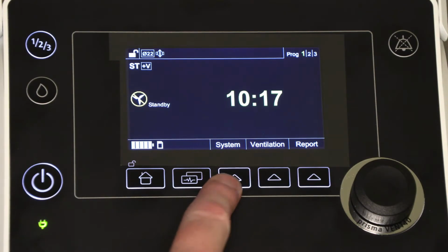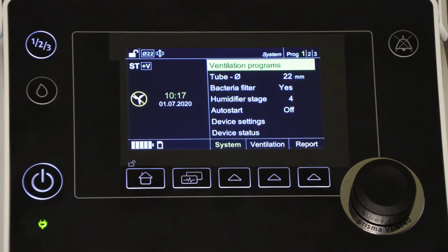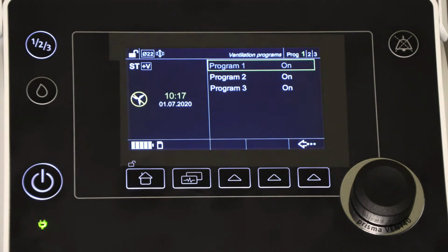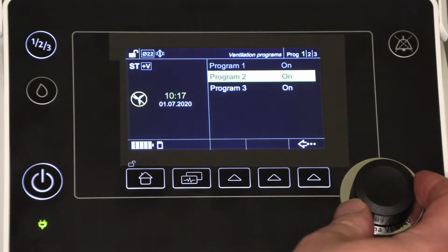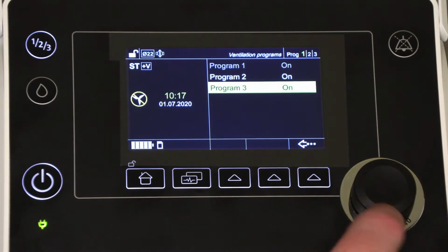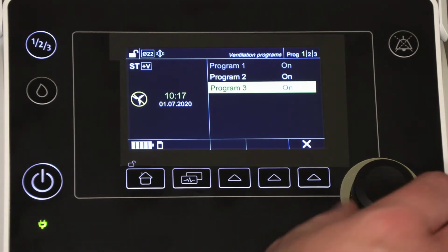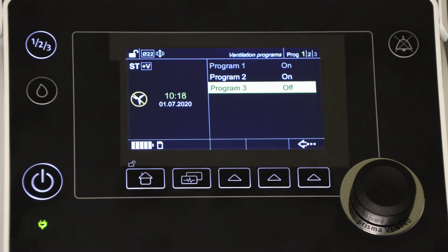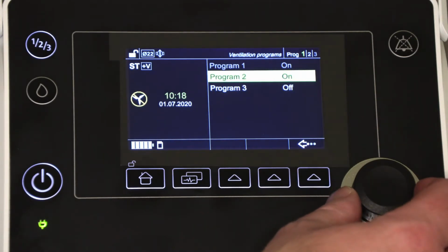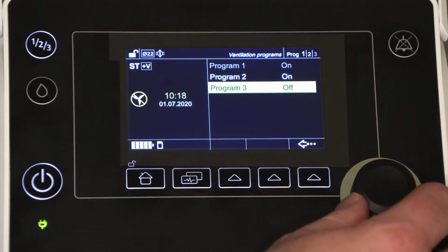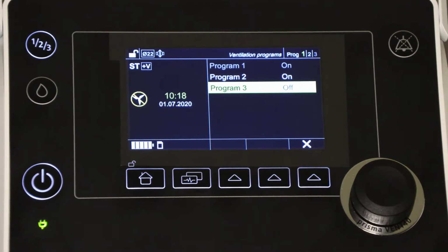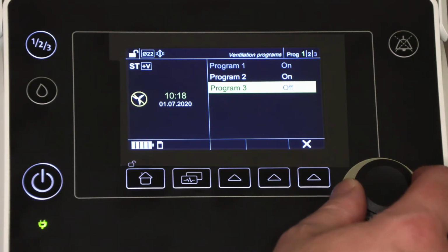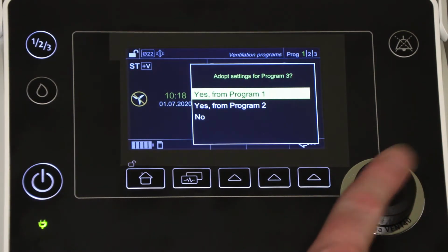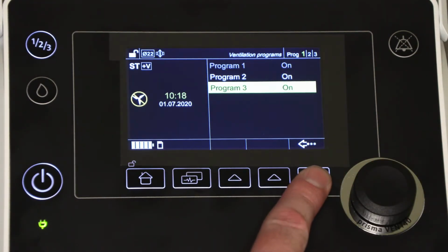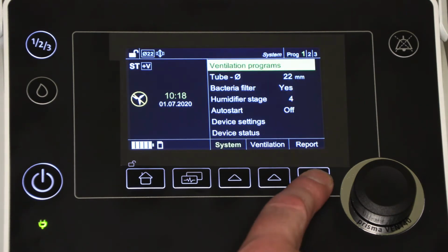In the system menu, the first item is ventilation programs. Press the rotary knob to enter this part of the menu. The status of each of the 3 available ventilation programs or profiles will be displayed. If you require more than 1 ventilation program to be available to the patient, then 2 or more of the programs must be set to on. To change the status of any ventilation program, turn the rotary knob to select it. Press the rotary knob to highlight the setting, then turn the rotary knob to change it and press it again to confirm. To go back to the System menu, press the back button at the bottom.